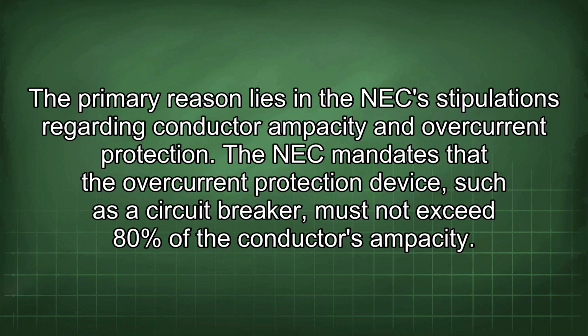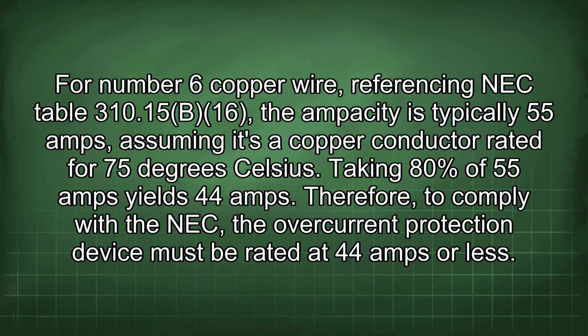The primary reason lies in the NEC stipulations regarding conductor ampacity and overcurrent protection. The NEC mandates that the overcurrent protection device, such as the circuit breaker, must not exceed 80% of the conductor's ampacity. For number 6 copper wire, referencing NEC table 310.15(B)(16), the ampacity is typically 55 amps, assuming it's a copper conductor rated for 75 degrees Celsius. Taking 80% of 55 amps yields 44 amps. Therefore, to comply with the NEC, the overcurrent protection device must be rated at 44 amps or less.